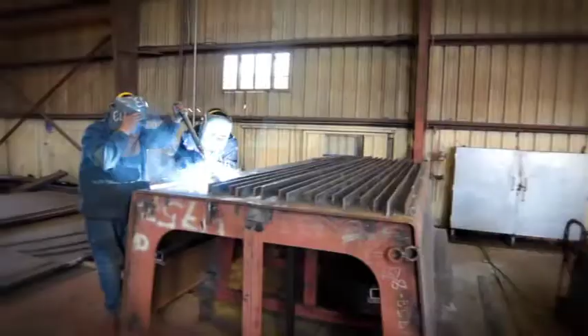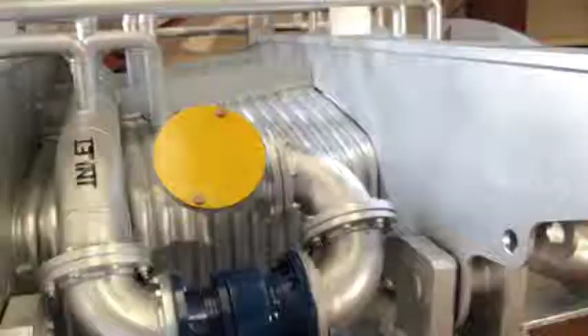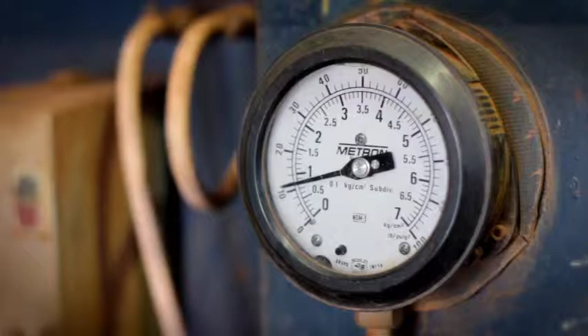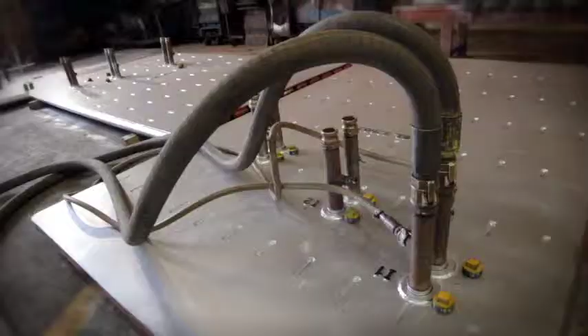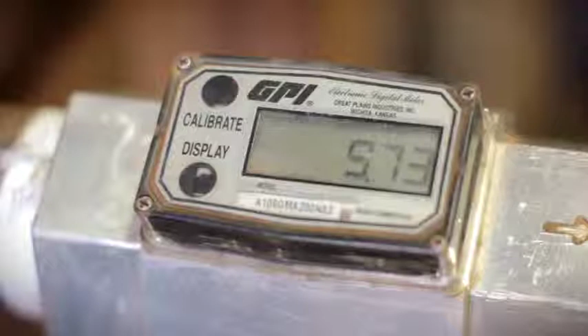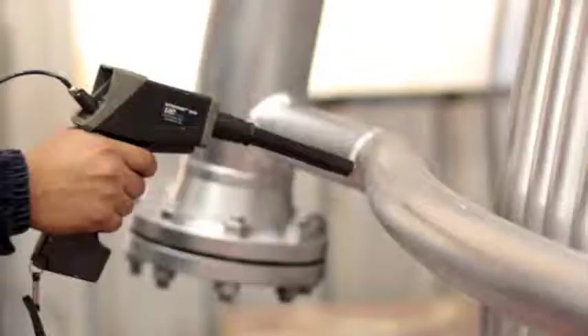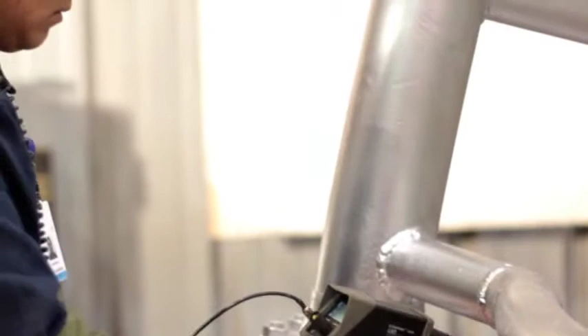This is certified by 3 tests we perform to all the pieces we manufacture: a pneumatic test after the root pass that guarantees the weld tightness, a flow test that confirms the circuits have free flow, and at the same time allow us to confirm that the real pressure drops are within limits of the theoretical one. This confirms the job was performed as per design.